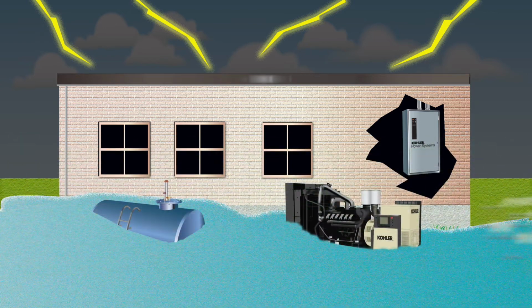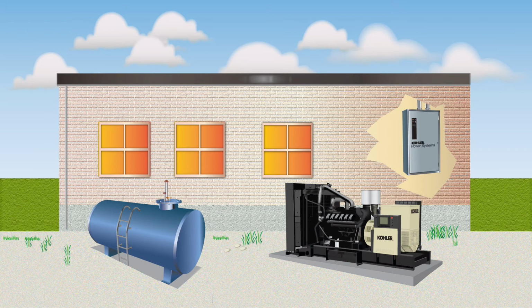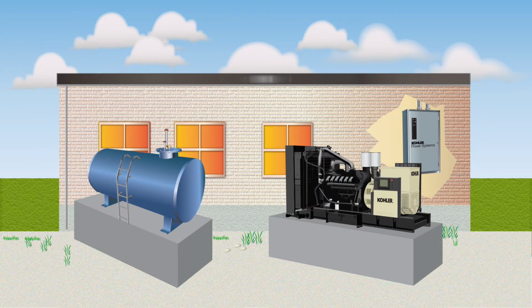FEMA determined standby systems installed at ground level in areas predetermined to be in flood-prone coastal areas were particularly exposed. A key recommendation of FEMA was to install generator sets and ancillary equipment such as fuel tanks and distribution panels above the flood line to ensure the equipment is safely above the flood level.